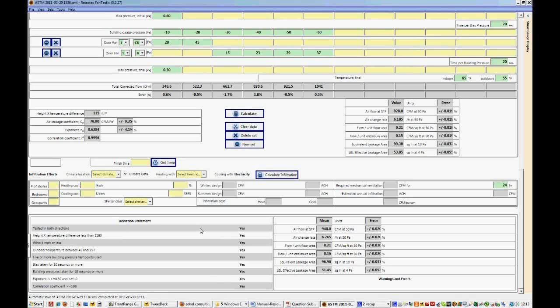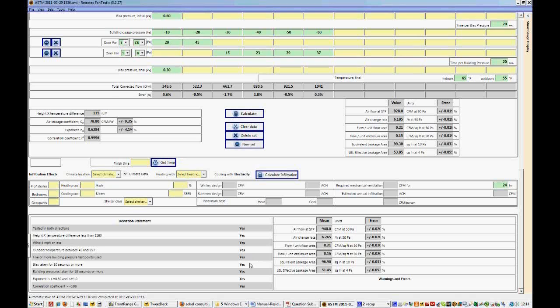Our height times temperature difference was less than 1180, and in both tests it was 115, so we satisfied that. Our wind speed was less than 4 miles per hour. Our outdoor temperatures were between 45 and 95 Fahrenheit. There were five or more building test pressures used, and we used 6 in this test. We did take our bias pressures for more than 10 seconds. We did it for 20 seconds. And as well, we did the building pressures for 20 seconds.